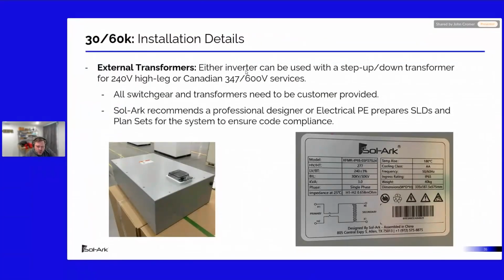For the 60K inverter, if you need to power the environmental controls of the outdoor cabinet, we have a transformer designed and built to fit inside the cabinet. It takes up a good amount of space, and by the time you get to about 4 cabinets or more, you probably want to pad mount your own transformer instead of going with the individual per-cabinet option, just from a cost perspective. But if you're doing a 1, 2, or 3 outdoor cabinet design, this is something to talk to your regional sales manager about, since it's not in distribution.